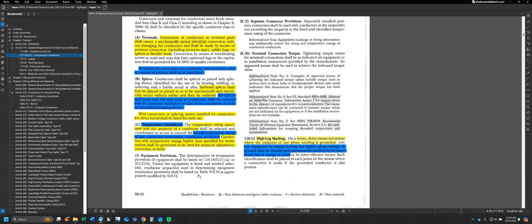Moving on to Part 1, it sets up Parts A and B. When selecting what temperature rating we can use to terminate a conductor, there's more to consider than just the insulation temperature rating. Even though THHN is rated under the 90°C column, that doesn't necessarily mean we can always use the 90°C ampacity. Part 1 tells us the rating will be based on 110.14(C)(1)(A) or (C)(1)(B).